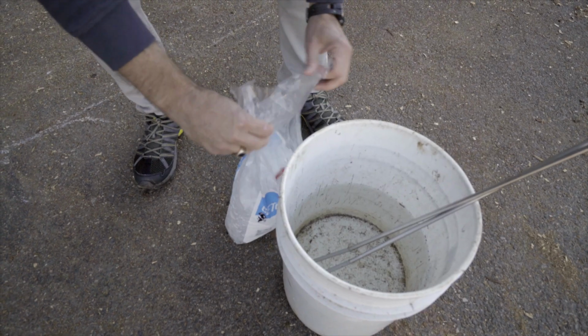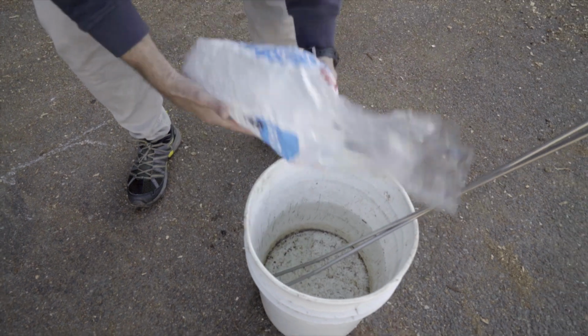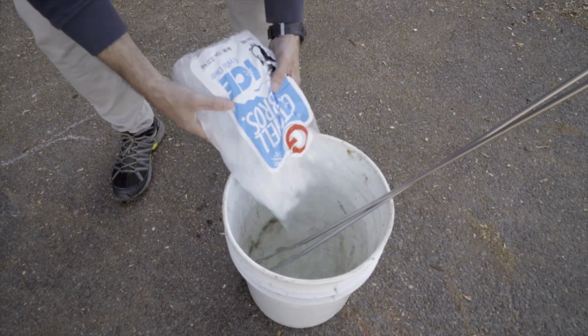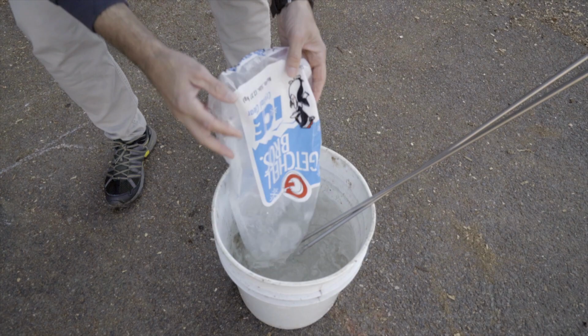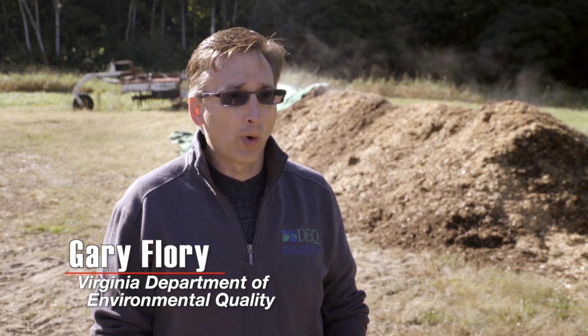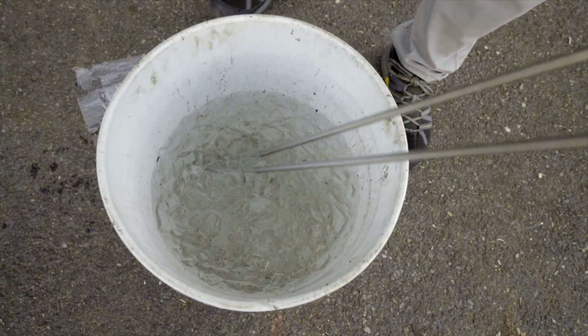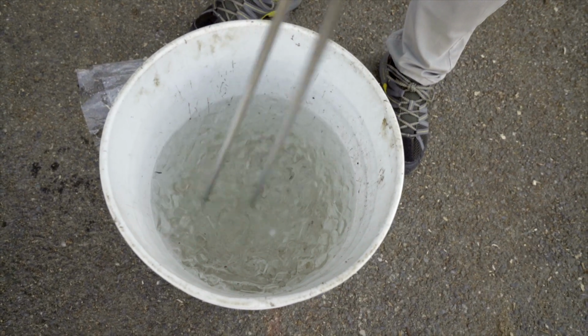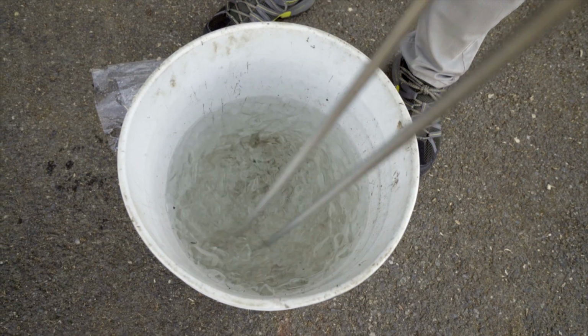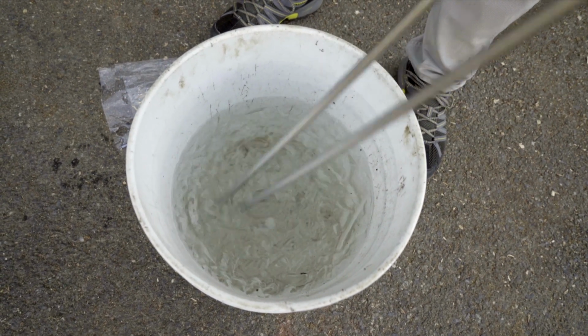To begin, you just need a bucket. A 5-gallon bucket is great. You can add water, about 6 inches to 8 inches of water into the bucket, and then add a bag of ice. Once you've added the ice to the bucket, you just need to give it about 60 seconds or so for the water to come to temperature. It might be more if the water is really warm or it's really hot outside. But once you add the ice to the water, you can stir it around with your temperature probe, and give it a few seconds, 60 seconds or so, to come to temperature.